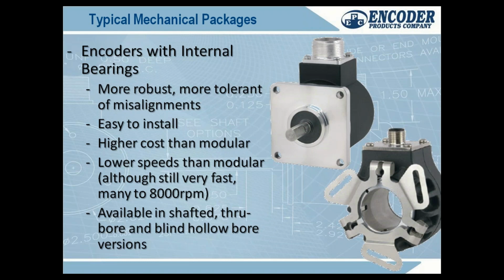So if you're putting these encoders in an application where there is going to be misalignment or shaft runout or high vibration, you'll want an encoder with bearings. The reason is by having bearings, we have a bearing on the shaft. Inside this encoder, we just saw a picture, right? There's a glass disc on the end of this with a read head. That glass disc has got to stay central to that read head. If it runs out just a little bit, you're going to introduce inaccuracy, and then you're going to crash it. So there's a nice set of bearings in here that keep it all centralized.